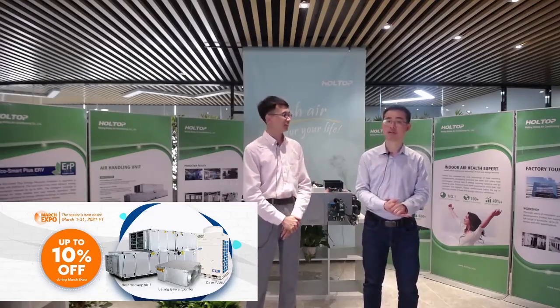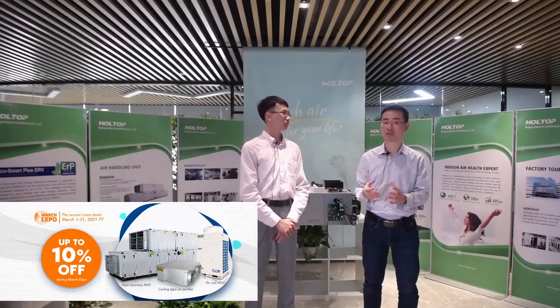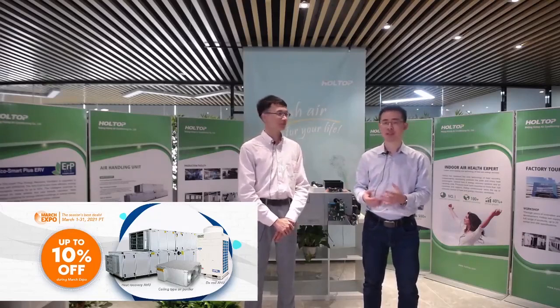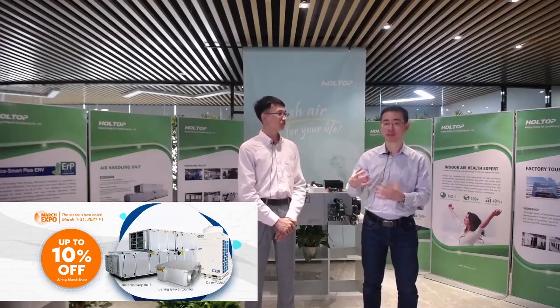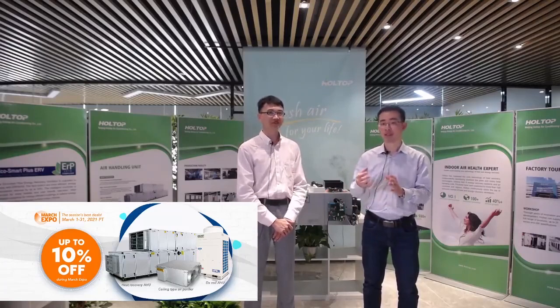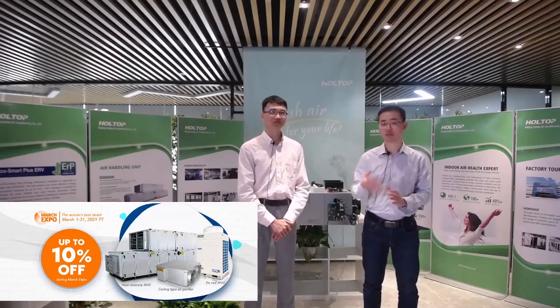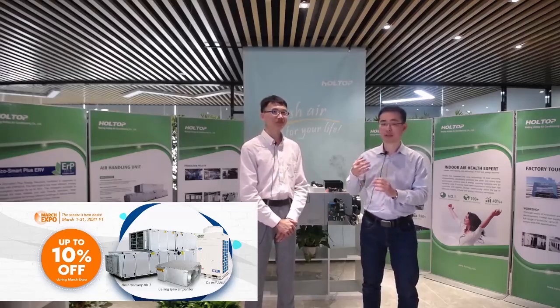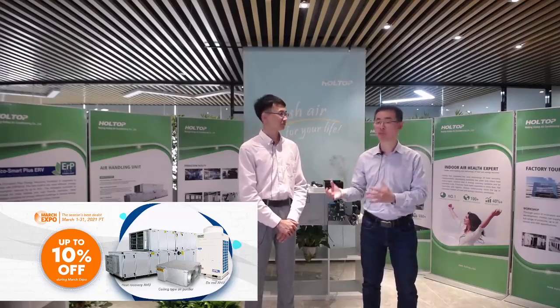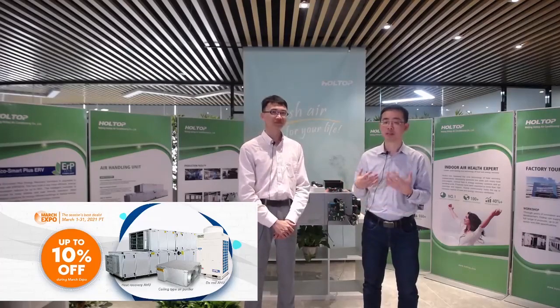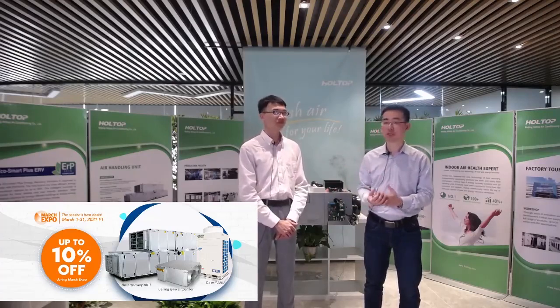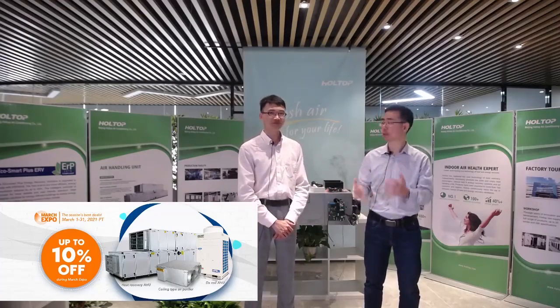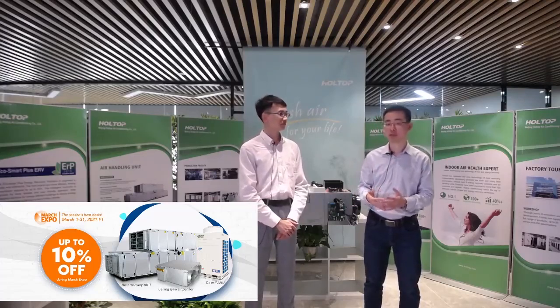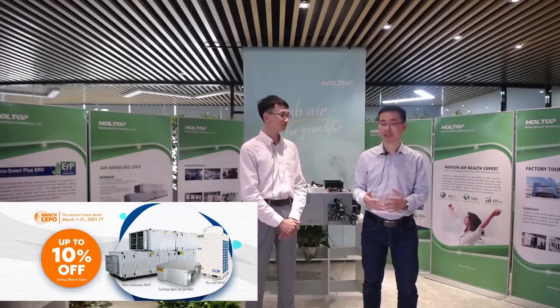Air-to-air heat recovery is our core technology at Holtop. We have been producing such equipment for over 2 decades, so we have very strong items for air-to-air heat recovery. For an office, it is a very good idea to use heat recovery, because a lot of people work in the office and need clean, fresh air. But since the indoor space has air conditioning, you need air-to-air heat recovery devices to reduce the energy consumption of the air conditioner. For offices, we normally recommend the ceiling type and plate heat exchanger. This would be a nice solution.